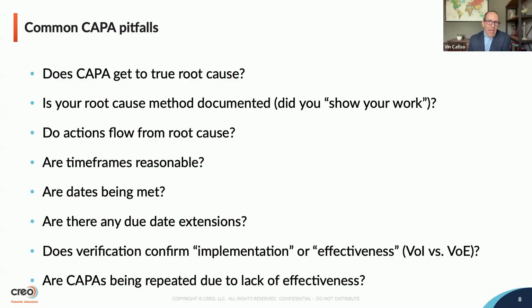Well, we don't want to have a recall, and hopefully we don't have more than one a year or something like that, right? So it will take you really a long time to do effectiveness for something like that. So you might actually have to do a mock recall just to be able to demonstrate that when you do this, the actions that we took are actually effective. So you have to get creative sometimes with effectiveness checks, but make sure that they are not just verifying that we did what we said we were going to do.